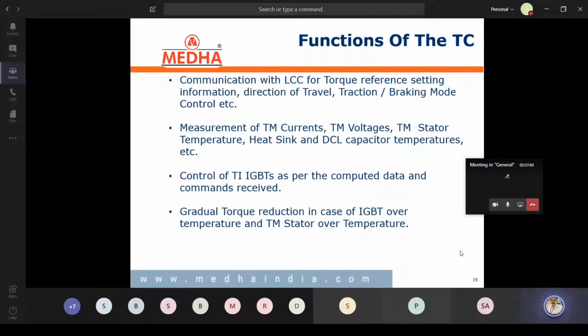Individually, where the particular problem is coming, for that particular motor only torque will be derated. And next, control of TCC blowers based on the IGBT heatsink temperature. Continuously the IGBT heatsink temperature in each and every converter or inverter, total there were 6 IGBTs. Each and every IGBT temperature is being monitored by the system computer, and from a safety point of view, out of 6, the higher value will be taken into consideration.